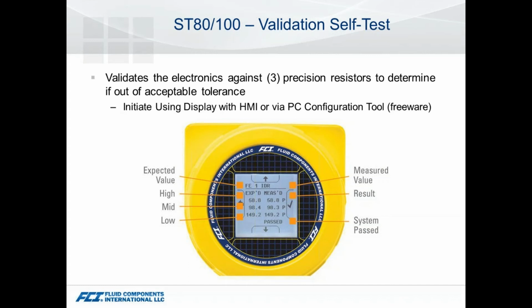Going to the higher end product, one feature that sets it apart is the ability to do this validation self-test. This is on the ST80/100s. Internal to the device, there are 3 precision resistors, a high, a medium, and a low setup. It's not any specific flow rate for that particular unit, but it gives us the ability to bypass the sensor itself and check that our electronics are still receiving the right inputs. We're not seeing issues such as drift.